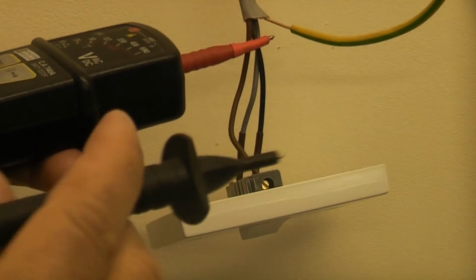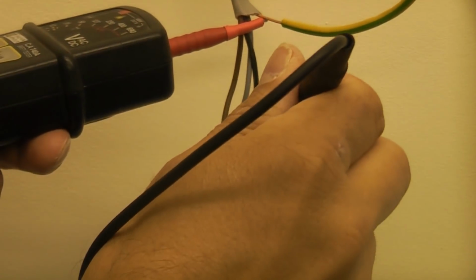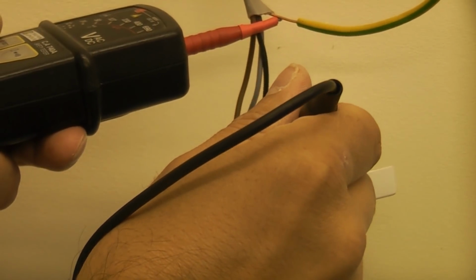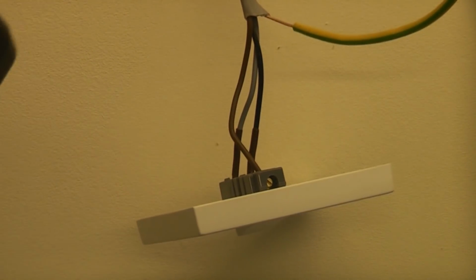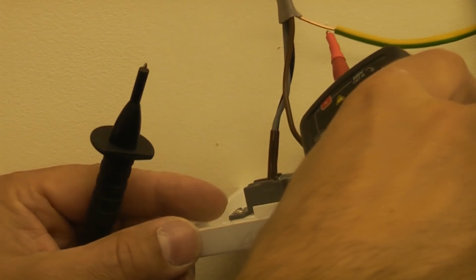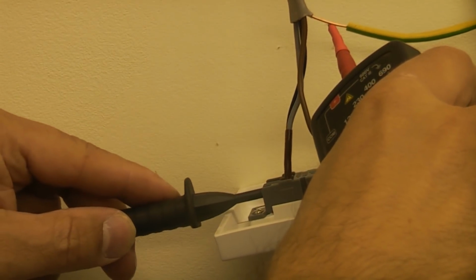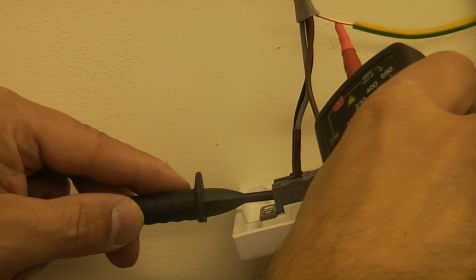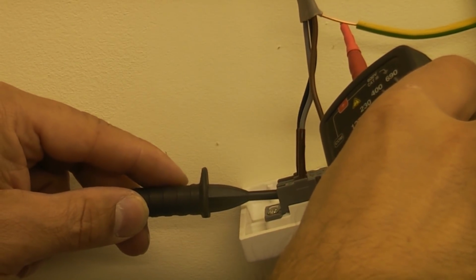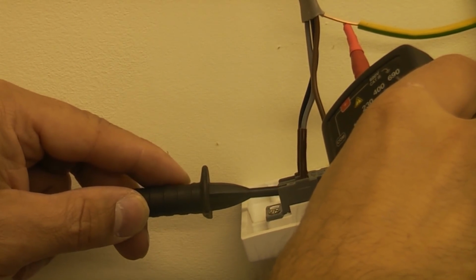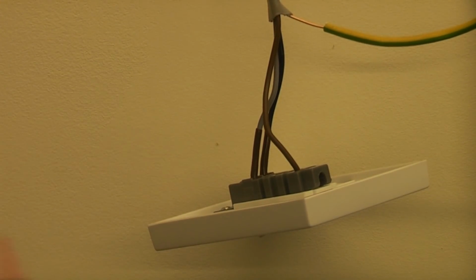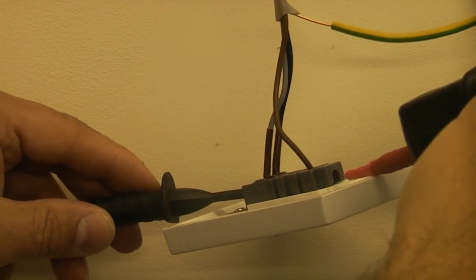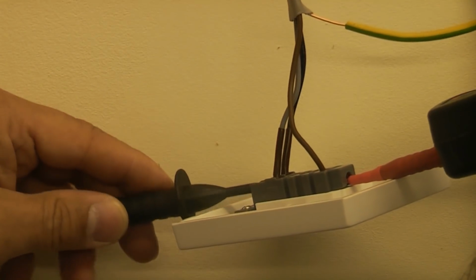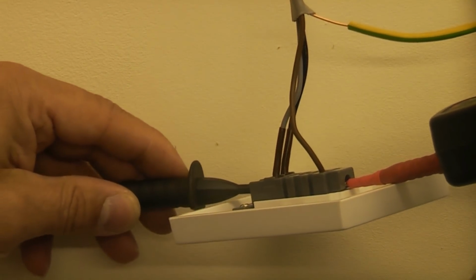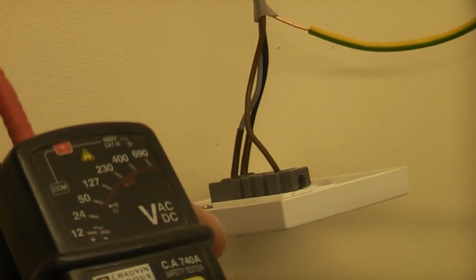So I'm going to put the probe on the earth wire, and then I'm going to probe the top terminal. And then I'm going to probe the bottom two terminals. And then we're just going to test between the wires. So I'll test between the common and the L2 and the common and the L1. And the tester isn't lighting up at all there, so we can safely say that that is isolated.